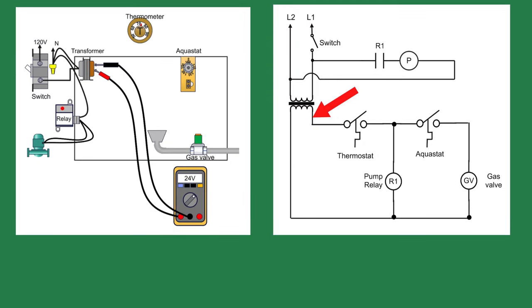My next step is to check the transformer. To do so, I connect meter leads to the secondary side of the transformer. We should have 24 volts across the terminals. It may be 1 or 2 volts higher or 1 or 2 volts lower.